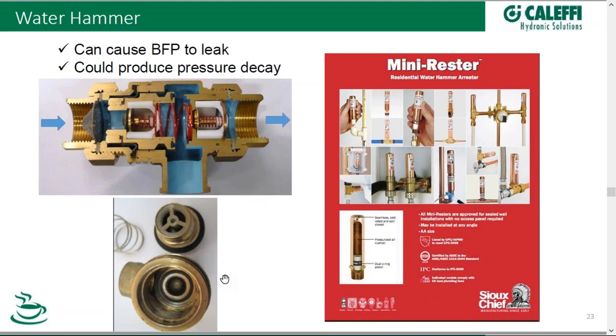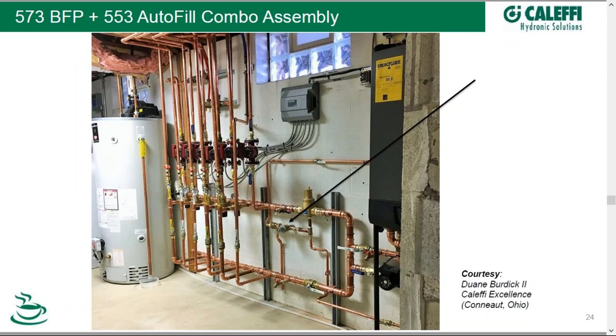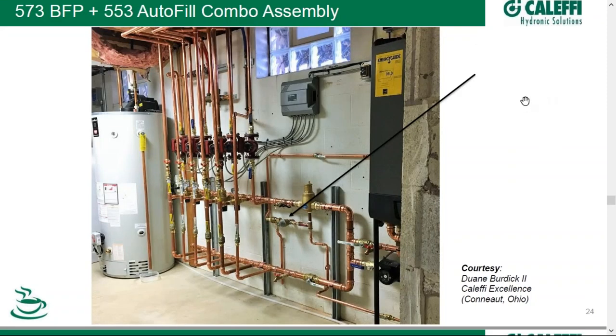It can be quickly taken apart and cleaned out with its union connections. To prevent water hammer to begin with, many arrestors or shock arrestors can be used to reduce that hammer effect. Here's an installation photograph of an autofill combo assembly from Dwayne Burdick of Ohio, submitted on Caleffi Excellence. Water comes in through the backflow preventer, into the autofill, and up into the system. More than likely he has an expansion tank connected over here — both the fill valve and the expansion tank connected under the bottom of an air separator, which is a common practice. The backflow preventer drain is within six inches of the floor per code.